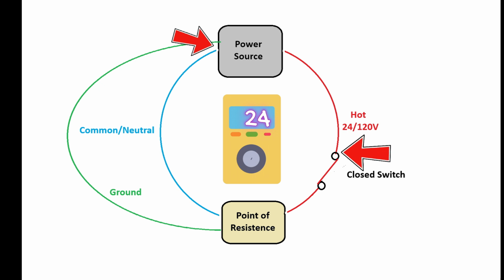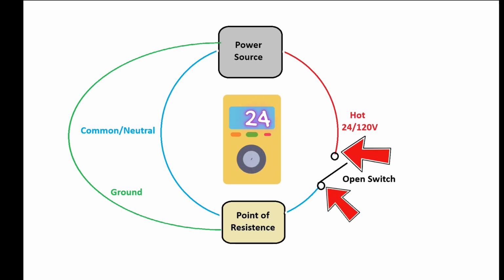Regardless if that switch is open or closed, once I can confirm I have voltage there, I now know I don't have a power problem. So if I move my probe to the reference point on the other side of that switch and I'm reading 0 volts, I now know I have a closed switch, because that switch has no resistance to it, there is no potential difference, and so I will be reading 0 volts. If I read 24 volts, I now know I have an open switch.